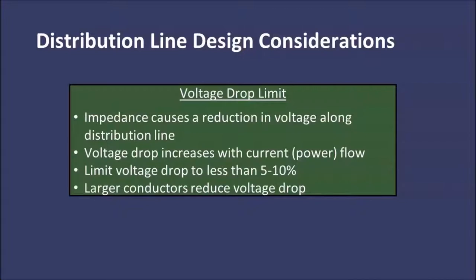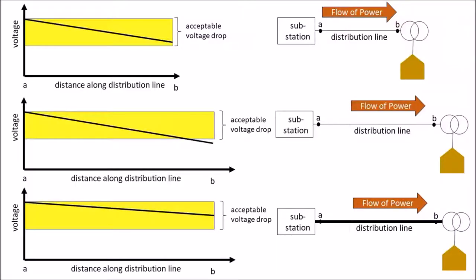One of the main considerations is voltage drop. As we send power down the distribution line to the community, the current encounters impedance, and the voltage drops along the line. We want to design the line so the community at the end has high enough voltage for TVs, lights, and so forth to function properly - usually a voltage drop of no more than 5 or 10%. If the voltage drop is too large, we'd pick larger, more expensive conductors. I'll show you a few examples of what this looks like on the next slide.